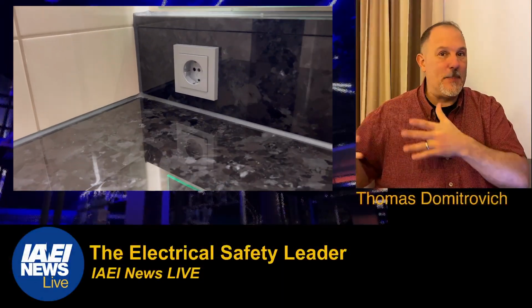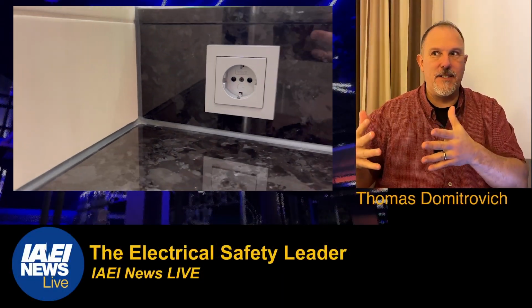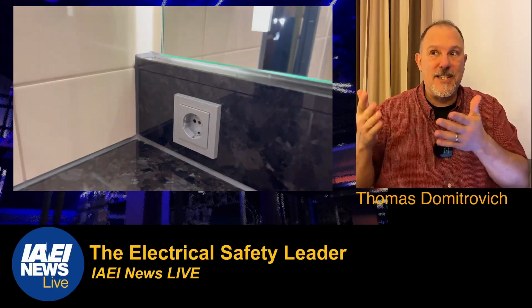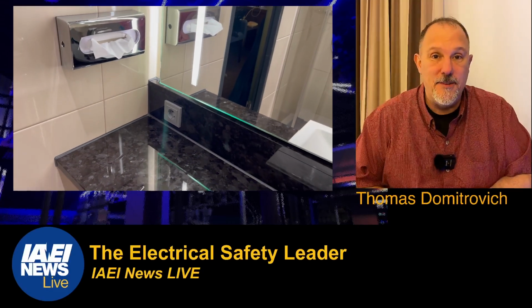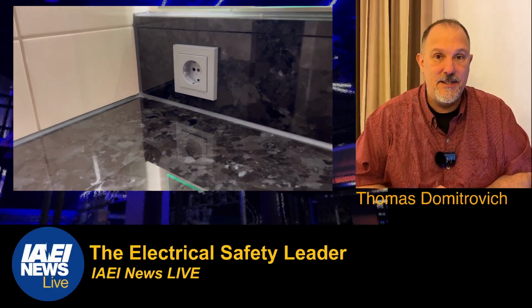Remember the Germany experience here with wiring devices. There's no push-to-test button in the bathroom on GFCIs. What they do in these applications over here, they have a 300 milliamp device on the main service overcurrent device. Then they have 100 milliamp, 30 milliamp on the branch circuits.